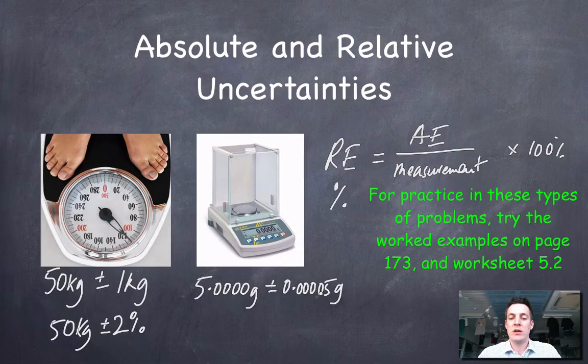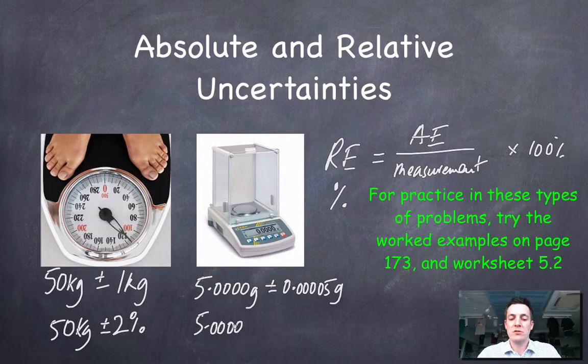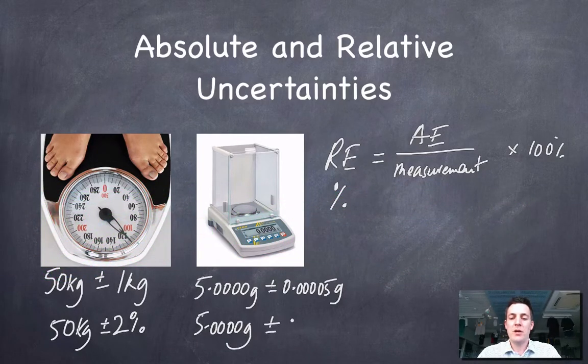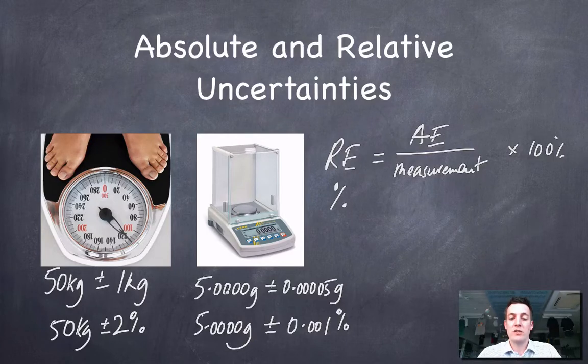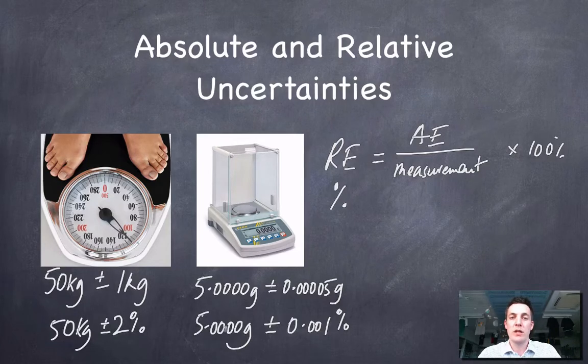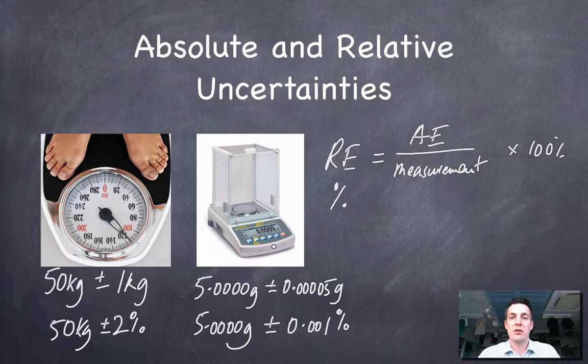What's the relative error for the 5 gram balance reading? We put this very small number on top and the relatively large number on the bottom, and we find a mass of 5.0000 grams plus or minus 0.001%. That's a very small relative error. But if I'd weighed an object of only 0.001 grams, this absolute error would become quite significant — the relative error would be much, much larger. Relative errors change in size depending on the reading, whereas absolute errors simply depend on the equipment.